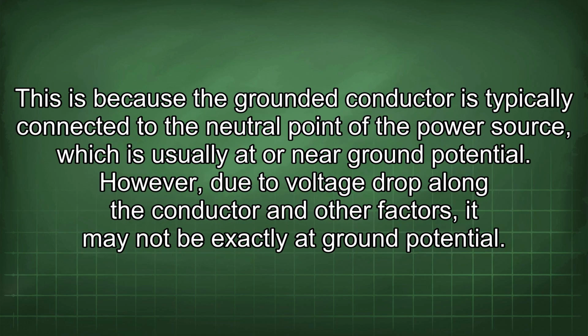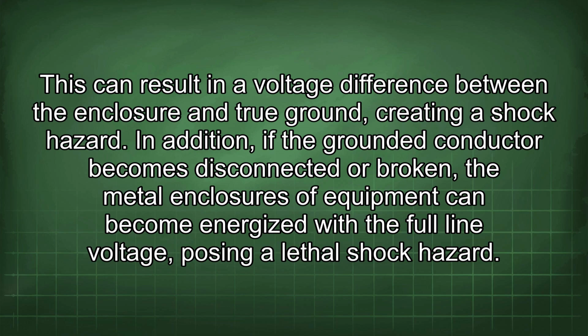This is because the grounded conductor is typically connected to the neutral point of the power source, which is usually at or near ground potential. However, due to voltage drop along the conductor and other factors, it may not be exactly at ground potential. This can result in a voltage difference between the enclosure and true ground, creating a shock hazard. In addition, if the grounded conductor becomes disconnected or broken, the metal enclosures of equipment can become energized with the full line voltage, posing a lethal shock hazard.